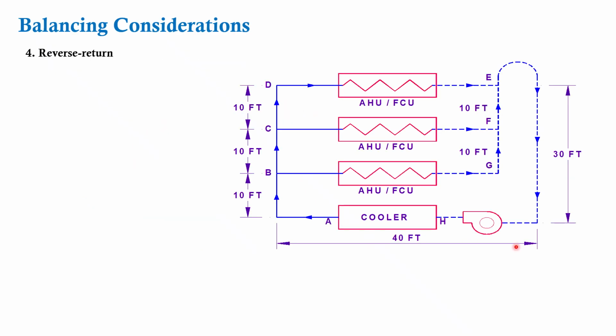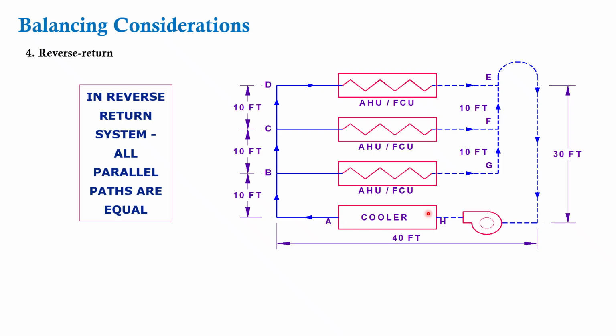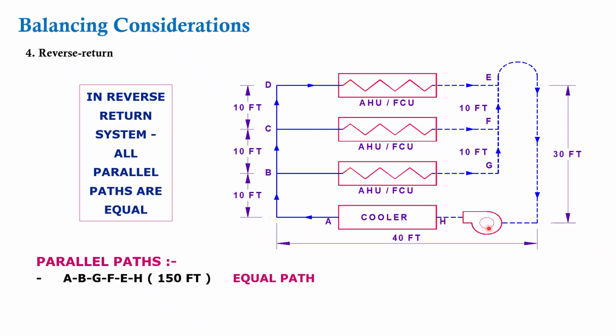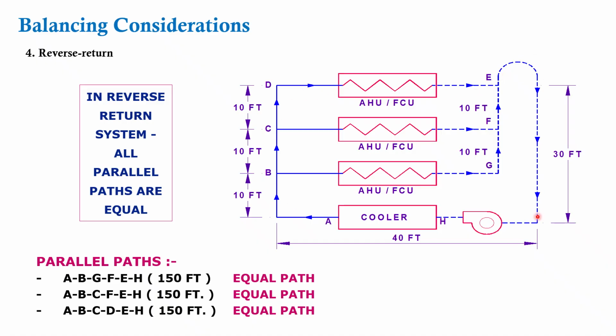Reverse return, I had already discussed, wherein there is a pump pumping water to the chiller, and then chilled water, which is at 7 degrees, goes to the first AHU, second and third, and the return of every AHU is connected to a common riser and comes back. So if you see, in a reverse return system, all parallel paths are equal, and this is how it is ensured. The first path is a distance of 40 feet, then 10 feet and another 40 feet, and this is going to be the common, so the 30 feet. So the total path is 150 feet in length. The second path is also 150 feet, and the third path is also 150 feet. So the reverse return methodology was used in the earlier days to balance the flow into every FCU or air handling unit.